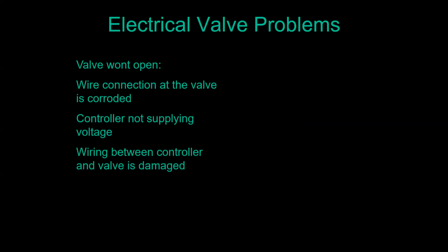Could be the wiring between the controller and the valve is damaged. Somebody was doing some digging and they cut your wires. It's unfortunate. It's more difficult to find. It's easy to find where somebody broke one of your pipes. Look for the big wet muddy hole. Try and find where they cut the wire and you're now leaking 24 volts of electricity in the ground.